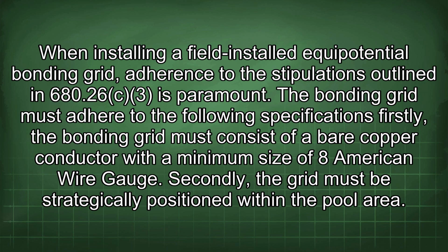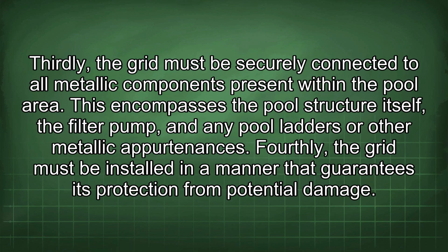Firstly, the bonding grid must consist of a bare copper conductor with a minimum size of 8 American wire gauge. Secondly, the grid must be strategically positioned within the pool area. Thirdly, the grid must be securely connected to all metallic components present within the pool area. This encompasses the pool structure itself, the filter pump, and any pool ladders or other metallic appurtenances. Fourthly, the grid must be installed in a manner that guarantees its protection from potential damage.